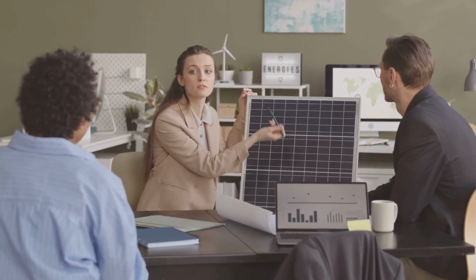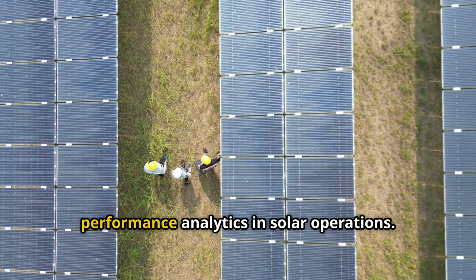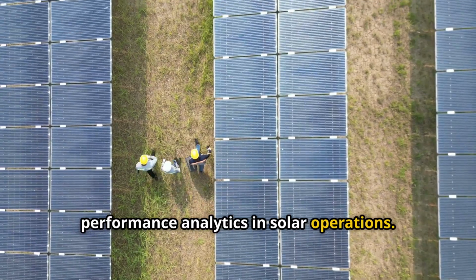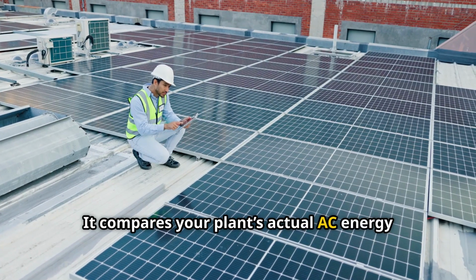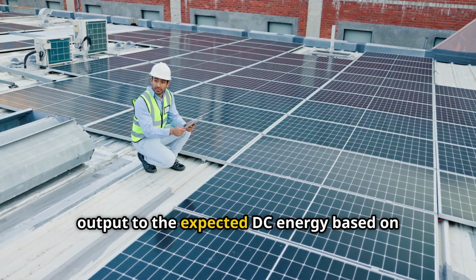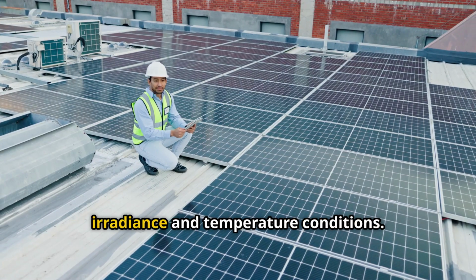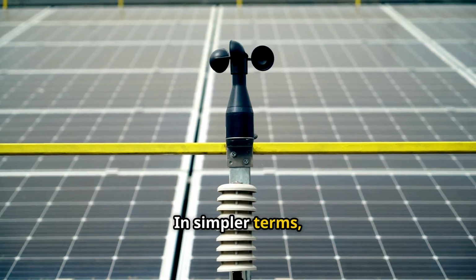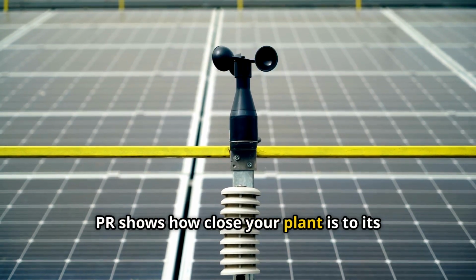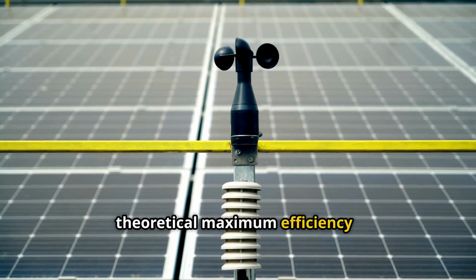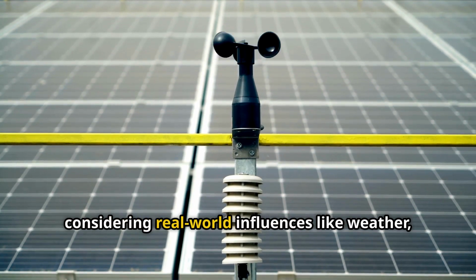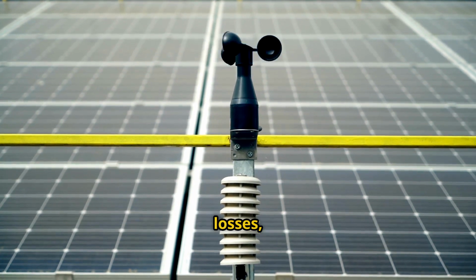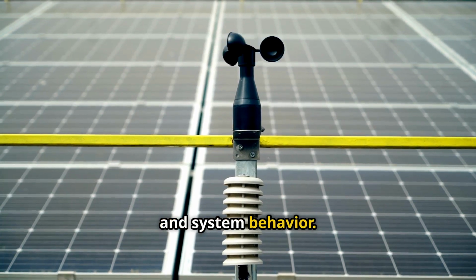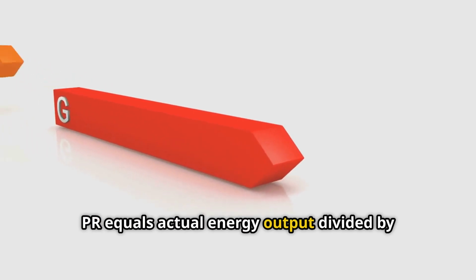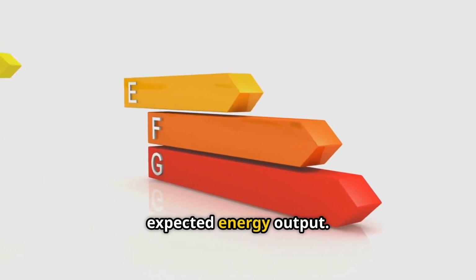Performance ratio is the heart of performance analytics in solar operations. It compares your plant's actual AC energy output to the expected DC energy based on irradiance and temperature conditions. In simpler terms, PR shows how close your plant is to its theoretical maximum efficiency. Considering real-world influences like weather, losses, and system behavior, PR equals actual energy output divided by expected energy output.